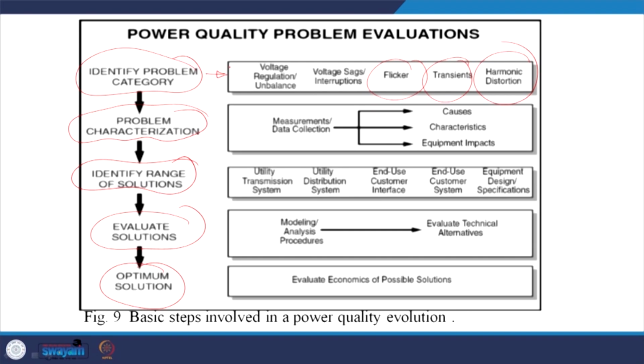Identify the problem category. Now, for problem characterization, you require to do measurement and data collection, whether it is a cause, a characteristic or an equipment impact, because THD is an equipment impact. Transient can be a flicker. Voltage interruption may be the loss of power. Then identify the range of the solution: the utility transmission system, who owns the responsibility, the utility distribution system, the end user customer interface, the end user customer system, and equipment design specification. So, this is all we require to revisit.